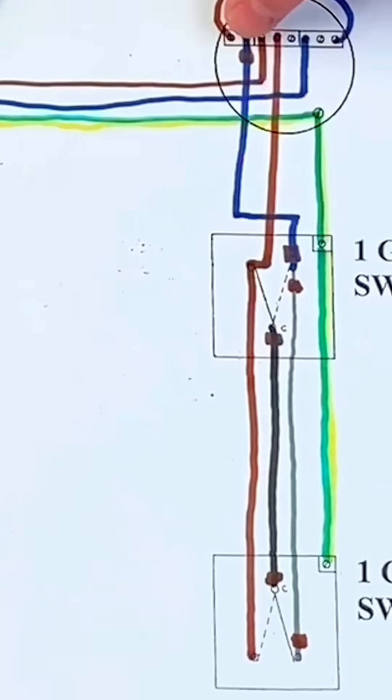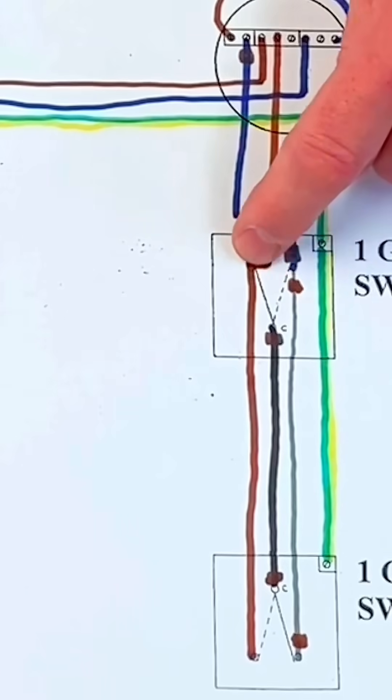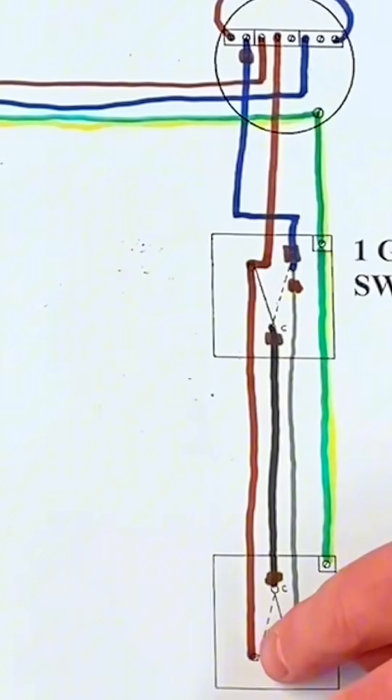Permanent line comes in through the loop down here. Well, this blade now is over to here, so it only goes down here, and this blade also is open so it doesn't turn it on.